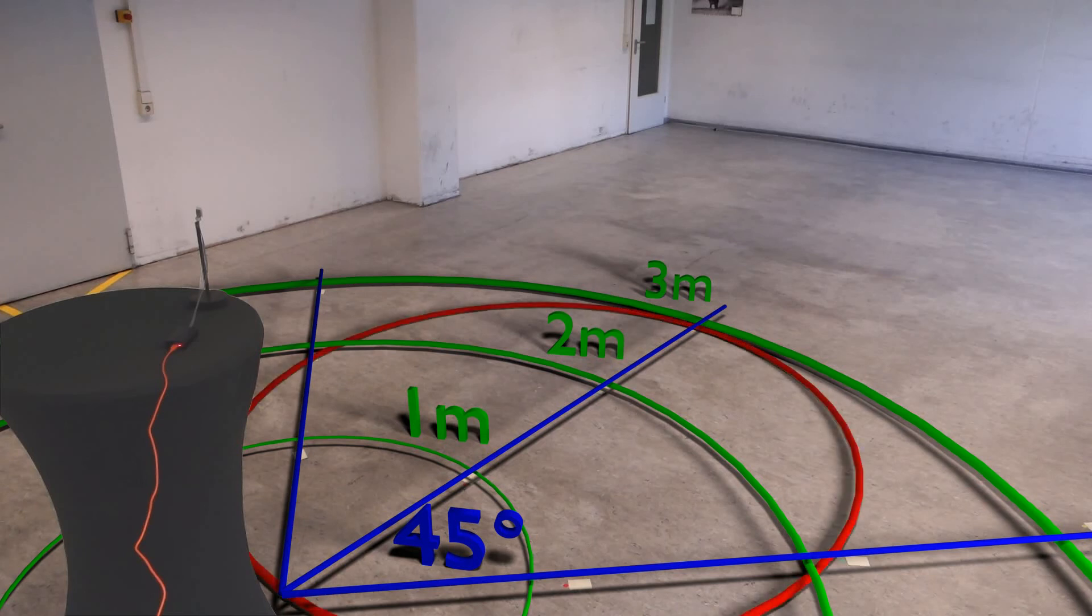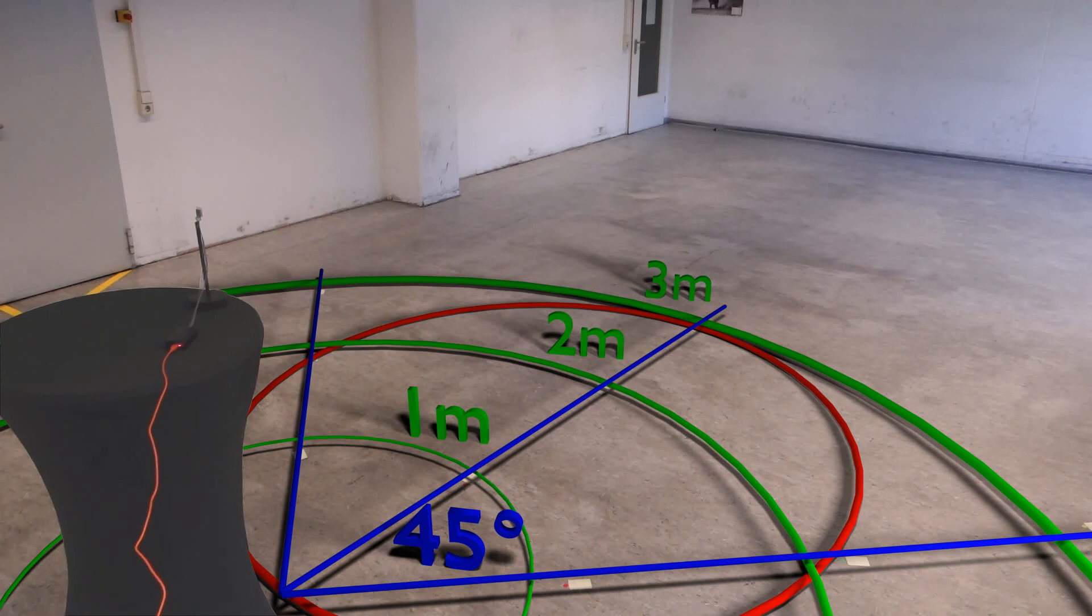The sensitivity is dropping with increasing angles, so that the maximum distance can be reached only at 0 degrees. Due to Lambert's physical law, you have to expect drop-down of 50% at an angle of 60 degrees.